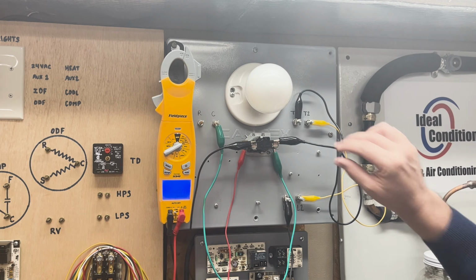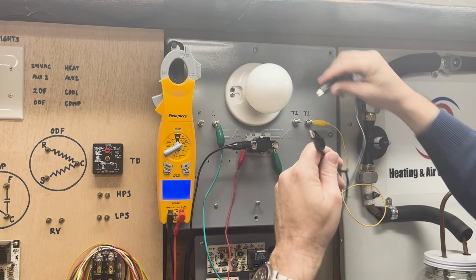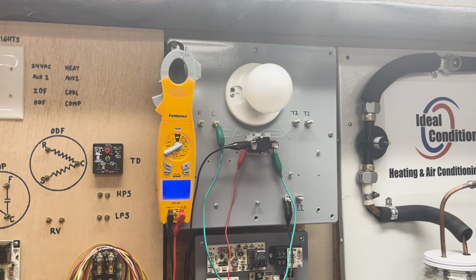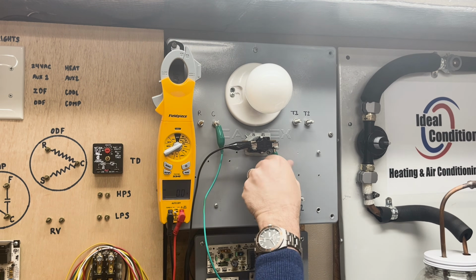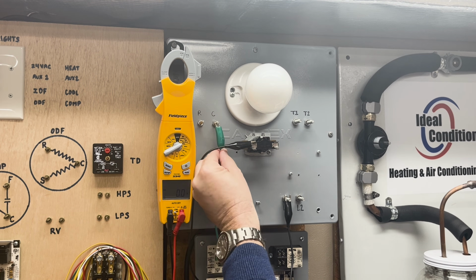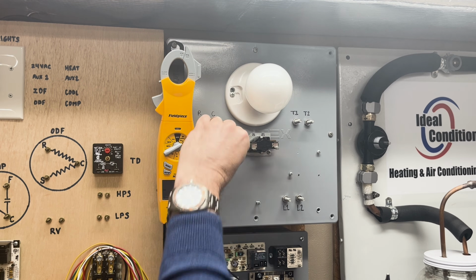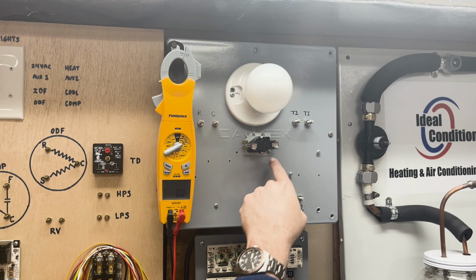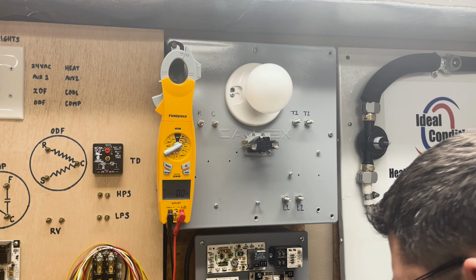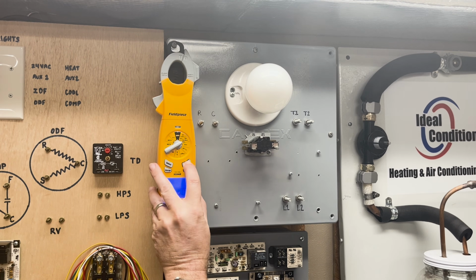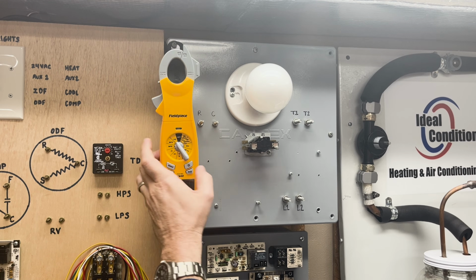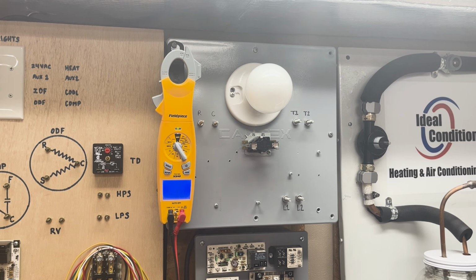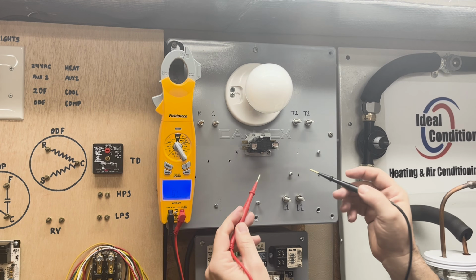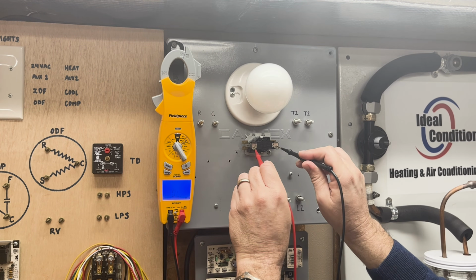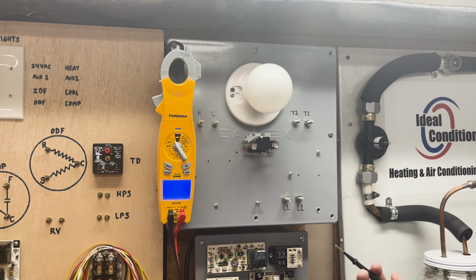So let's go ahead and take all these wires off. And what we're going to do is I'm going to show you the resistance, and I'm going to show you how I can tell if I have contact or coil. Now, like I said earlier, if you look, there's discolored terminals here. They're brass, and that's always going to be your coil side. If you just remember that, you're good. Let's see what we will have here if we come over to continuity. There's the ringtone with no numbers because there's no resistance. Just a ringtone. So we're looking for a ringtone. So this relay is open here and it's open here. It's a good relay so far.